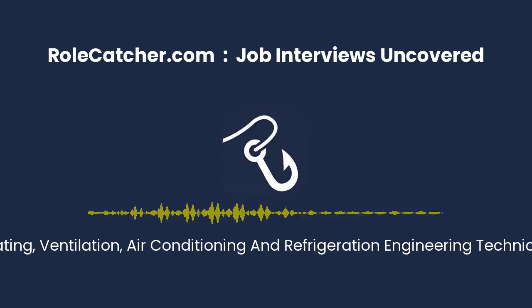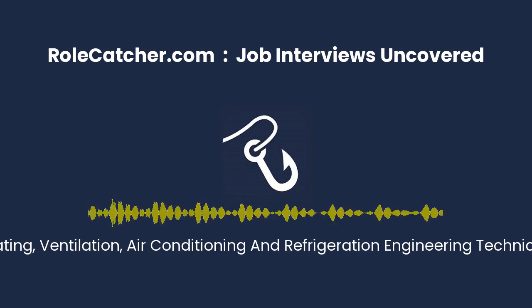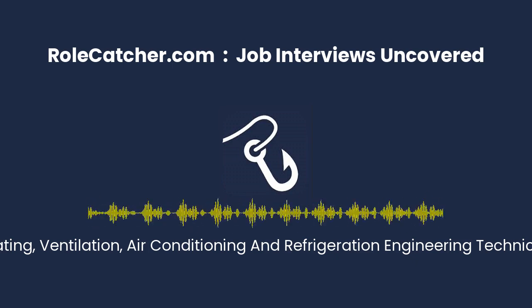Got it. So what if I said something like, I was working on this commercial refrigeration unit and it was having intermittent cooling problems. It would work fine for a few hours. Yeah. And then it would just stop cooling. And then it would start working again and we couldn't figure out why. Ooh, yeah, that's a good one. That's a real head-scratcher. So what did you do? So I started by checking all the usual suspects. I checked the thermostat settings, I checked the refrigerant levels, I looked for leaks. I inspected the compressor and condenser unit for any signs of damage or malfunction. But everything seemed to be in working order. So you eliminated the obvious stuff.